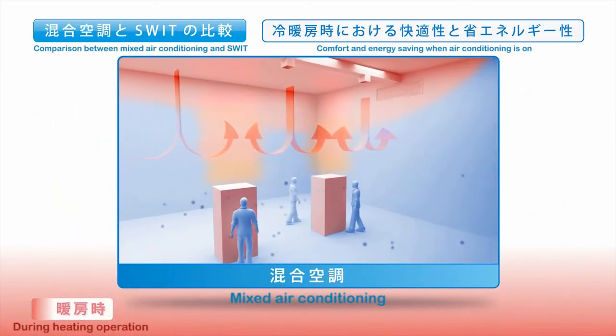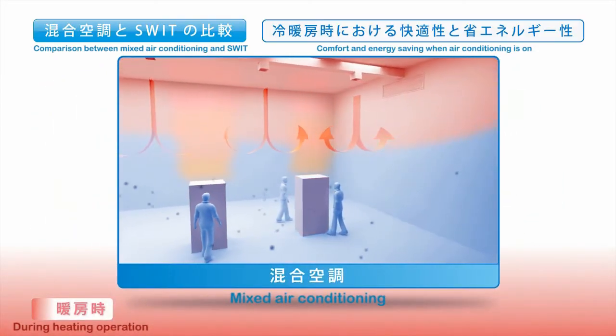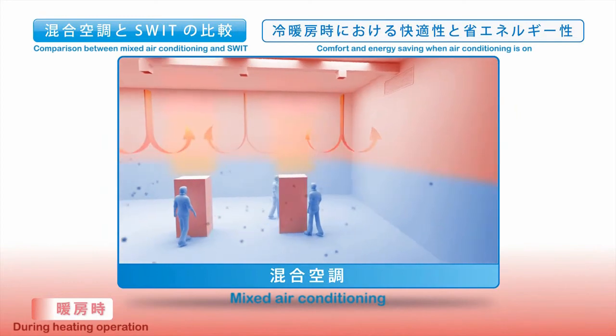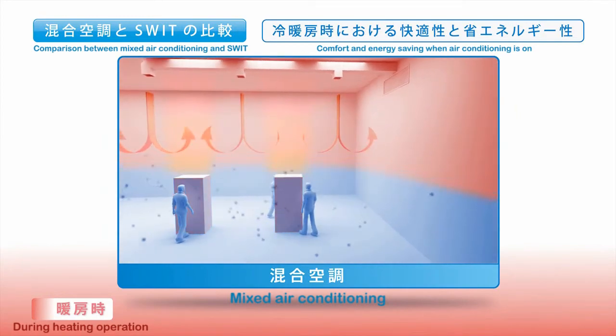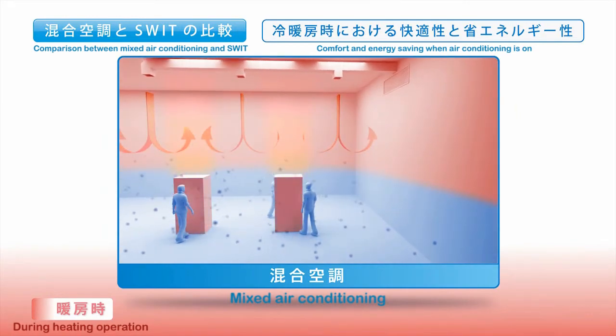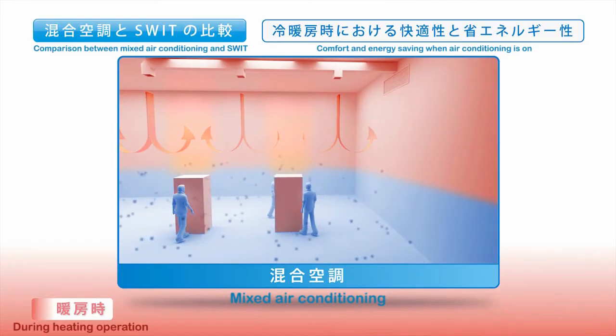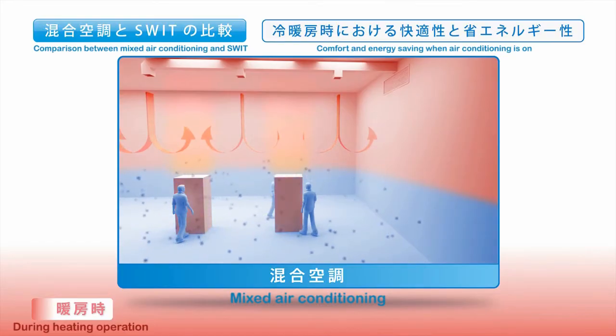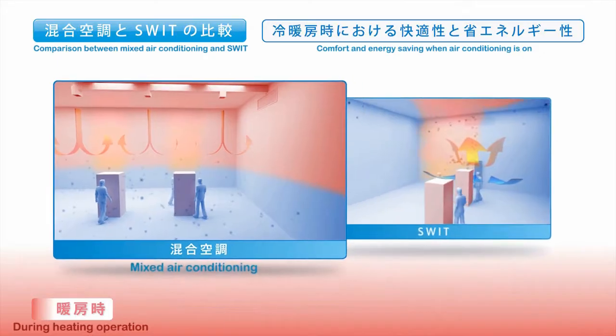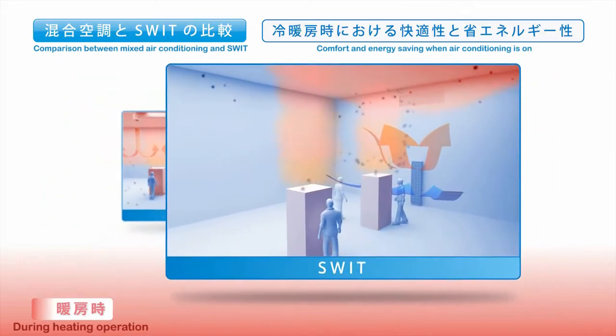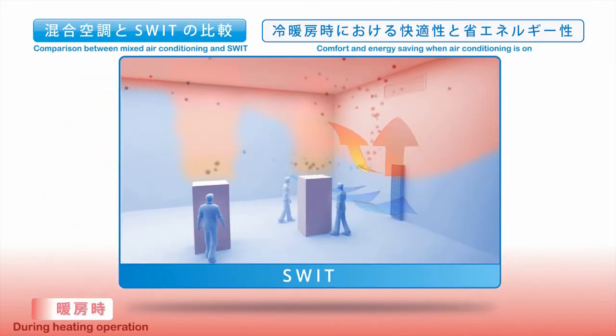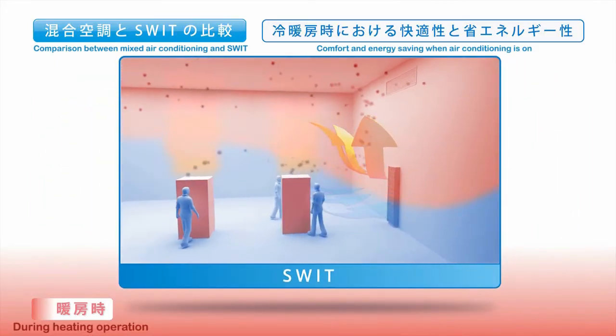During heating, cold air and pollutants stay in the living area with Mixed Air Conditioning, as it is difficult for the warm air supplied to reach the lower levels. Meanwhile, SWIT prevents cool air and pollutants from remaining by carrying them with the surrounding air up to the higher levels.